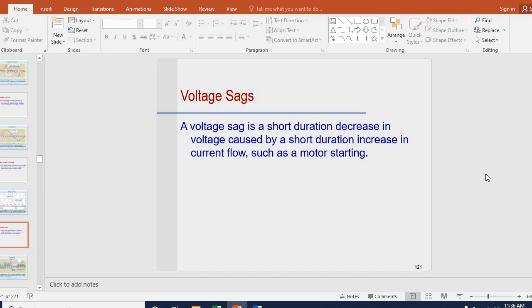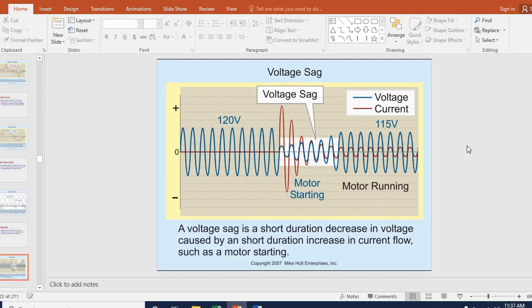Voltage sag is a short duration decrease in voltage caused by a short duration increase in current flow, such as a motor starting. So everything's rocking along and everybody's doing good, and all of a sudden your lights dim, and maybe in a plant you see the lights dim and flicker. Might be because they started up a big motor. Well, that big motor took a lot of energy and voltage current draw, which caused the voltage to sag, and there you go. It starts having problems from there. Then after a little bit of time, it straightens out. If your system can stand it, it don't cause problems. If not, you have problems.